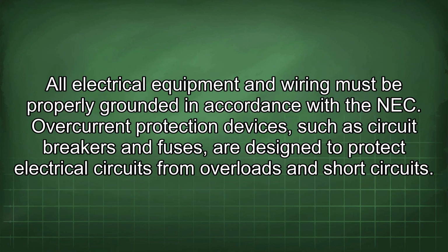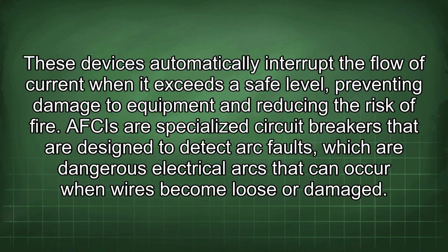All electrical equipment and wiring must be properly grounded in accordance with the NEC. Overcurrent protection devices, such as circuit breakers and fuses, are designed to protect electrical circuits from overloads and short circuits. These devices automatically interrupt the flow of current when it exceeds a safe level, preventing damage to equipment and reducing the risk of fire. AFCIs are specialized circuit breakers that are designed to detect arc faults, which are dangerous electrical arcs that can occur when wires become loose or damaged.